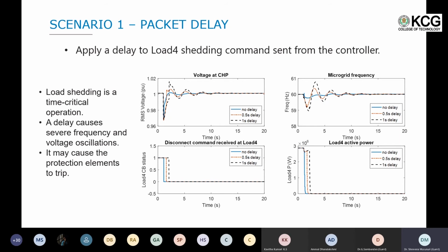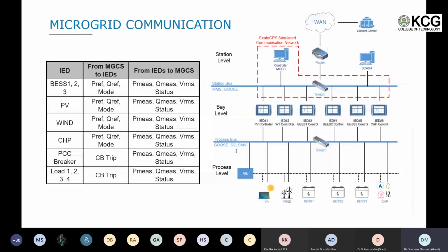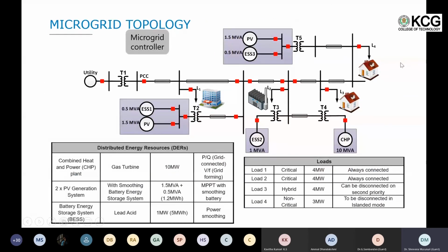Here is one case. As I was mentioning earlier, the entire microgrid was designed such that load 4, when a fault happens and this disconnect switch opens up, the balance was created in such a way that load 4 has to be disconnected immediately. Otherwise, you have a case where the load is more than the generation. A scenario was created like that, and the system will slowly go into instability mode.